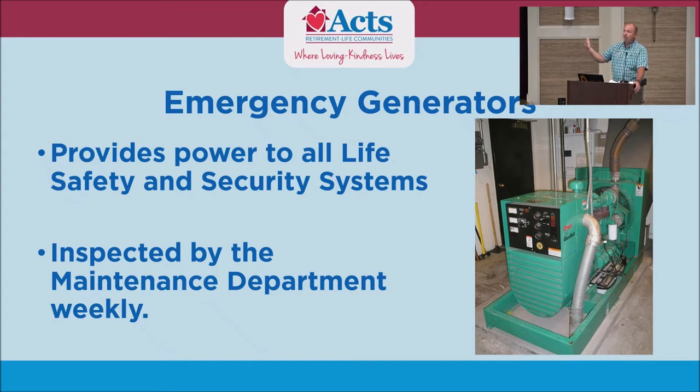In every OBT room, for example, there's one outlet on emergency power. There are outlets in the Willowbrook rooms. The generator runs our kitchen and a lot of stuff in the clubhouse — not everything, but a lot. The generator runs every Tuesday morning at 9:30 — it comes on and runs for about 30 minutes as an auto-start feature so we know the generator will crank.